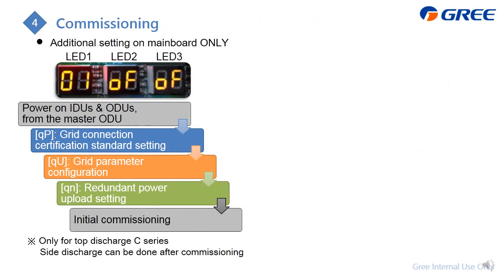And after that, you need to do the commissioning. This is especially for the top discharge and especially for the C series. So for that, just follow these steps. This is an additional step compared with the regular VRF, which includes QP, which is for the grid connection certification, and then QU is the power supply setting, and QN is whether you need to upload to the grid power supply, which standard is this one.